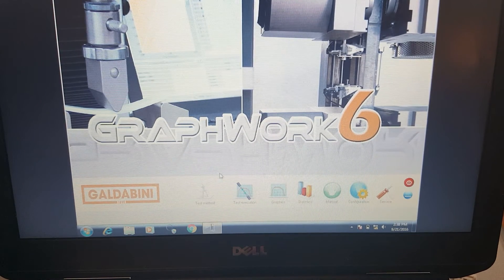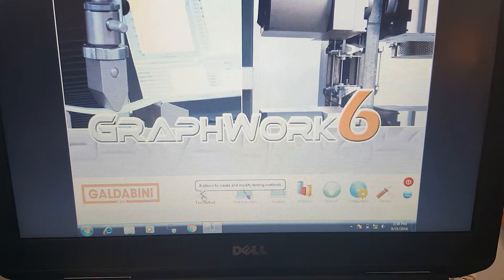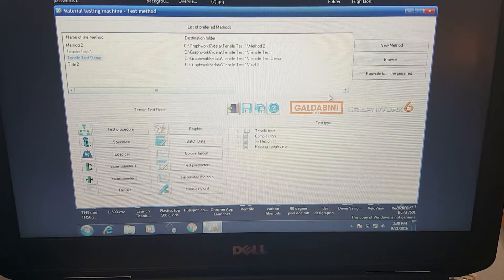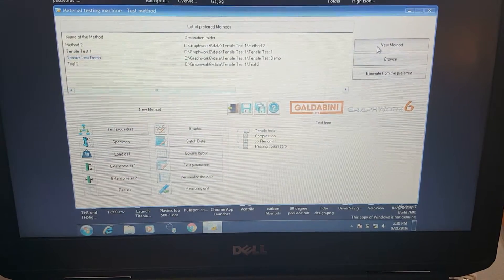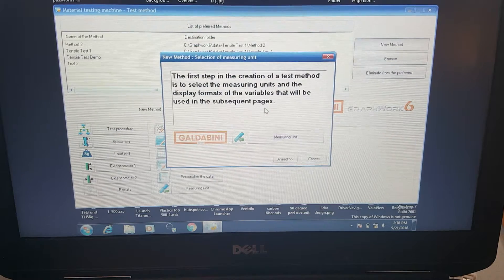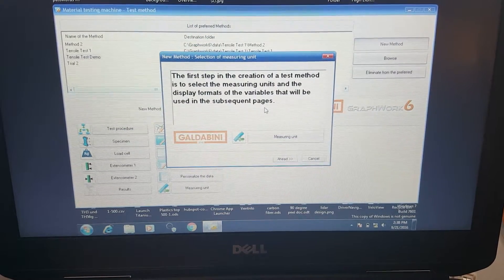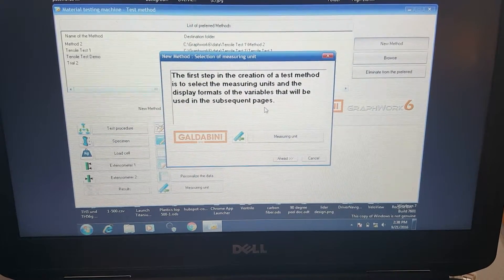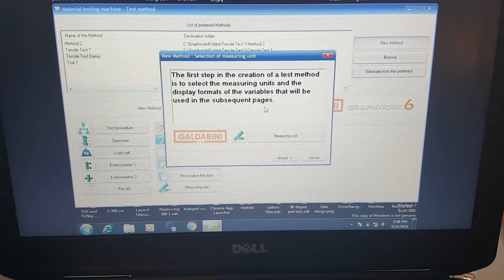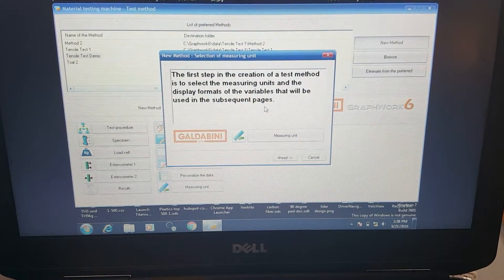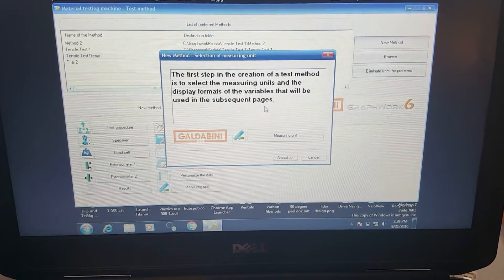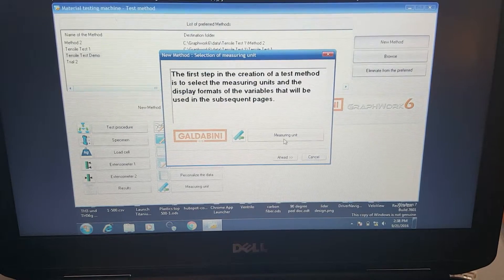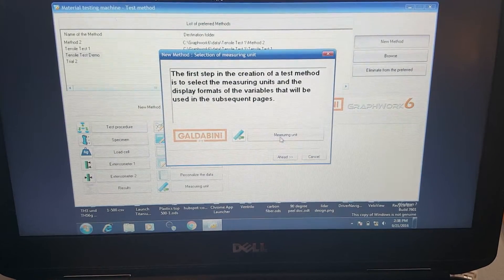To set up tests with GraphWork 6 is very easy. We go over a test method and choose a new method here. It's going to go right into a setup wizard. The setup wizard can be very easy to use or it can get more complex depending on exactly how you need the test to be and your level of expertise.